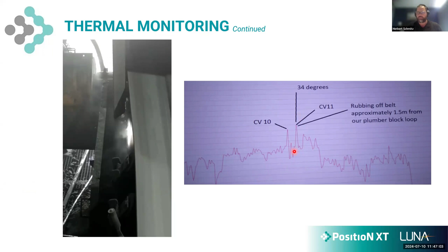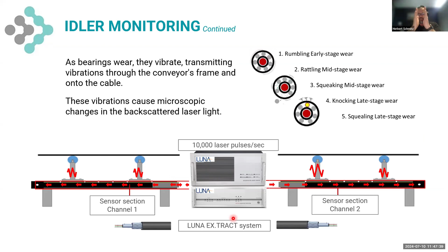Back to the condition monitoring part thereof, this is our vibration or acoustic sensing system, where we have 7 kilometers per channel. We have a resolution down to pretty much every single idler frame along a conveyor. What this system does is monitor, as a process run, every single frame along a conveyor. We interrogate the acoustic information at that frame, and we compare those acoustic signatures to known values, such as knocking, squealing, which has a very specific acoustic profile, rattling, squeaking, and rumbling, very early failures.